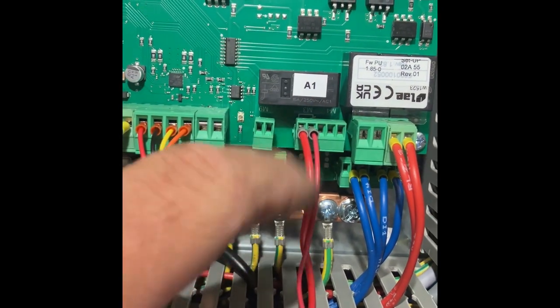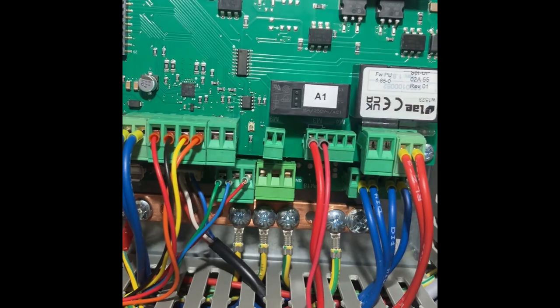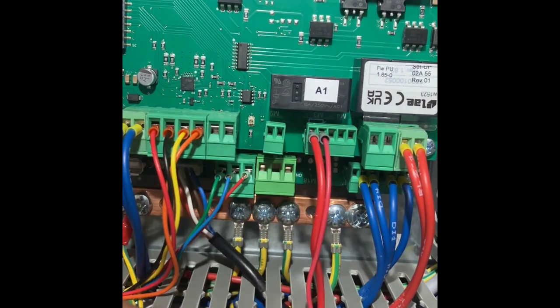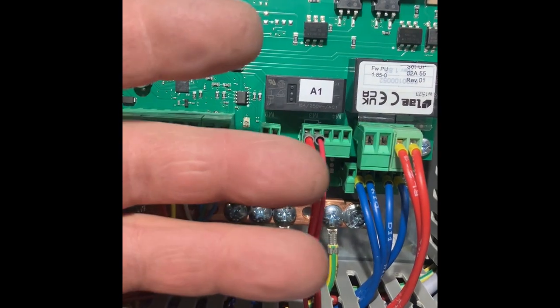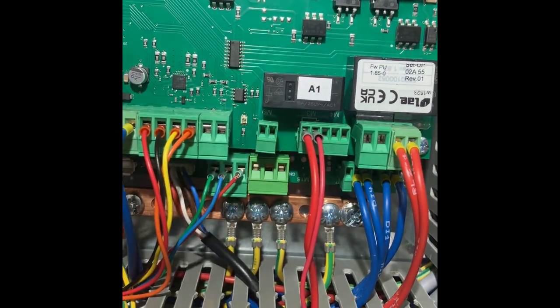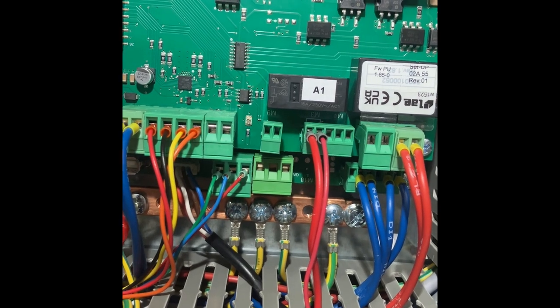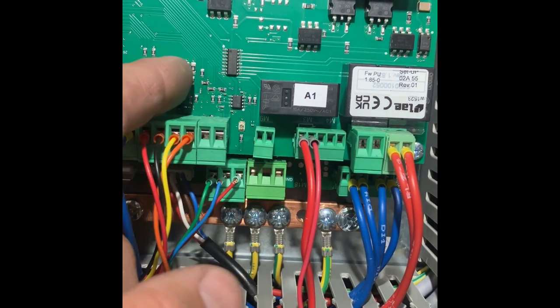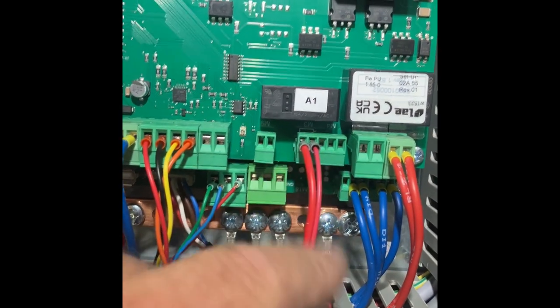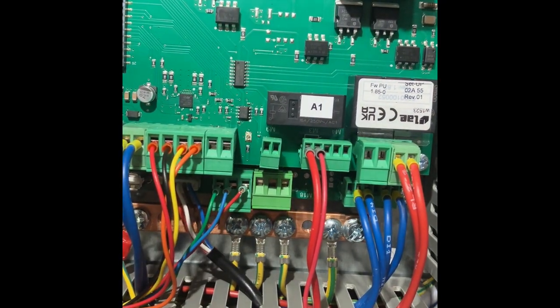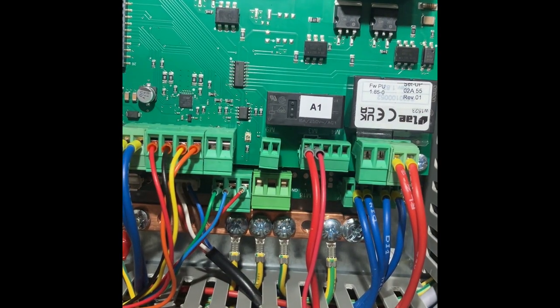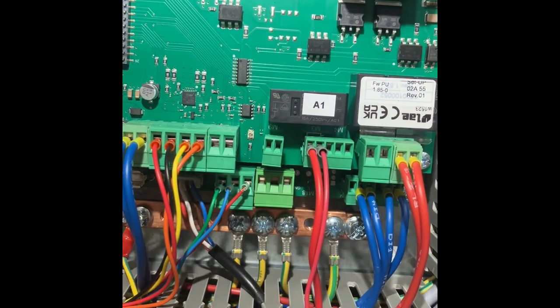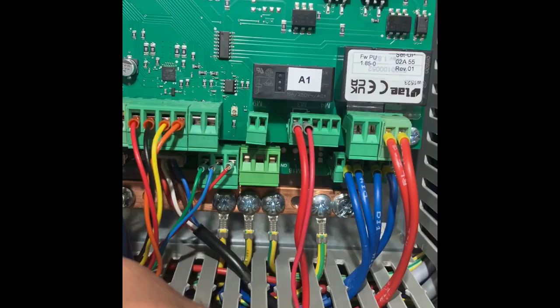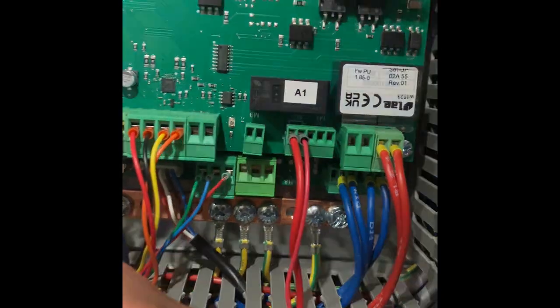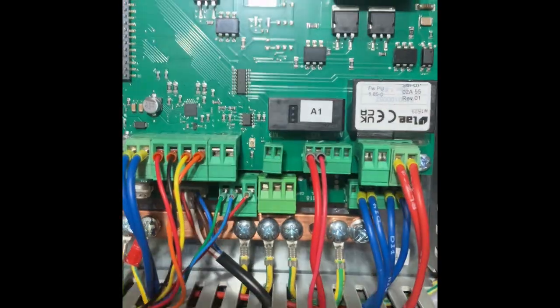So that's always something to check for when you're tying into any kind of contacts like that. It is technically a normally closed contact, because when power is off and this thing is in what we refer to as the shelf state, or the state that it would be in sitting on a shelf, these contacts are closed. As soon as this powers up, they open. So always be mindful of that when tying into any kind of contacts, whether they be alarm contacts or whatever. Just give them a quick check before you assume you know how they work, because some companies would actually label that as a normally open, and it's a real quick, easy check just to make sure you know what you're dealing with. So that's it for the dryer.